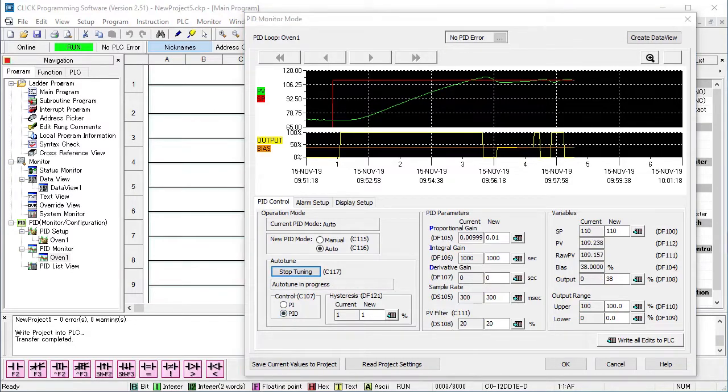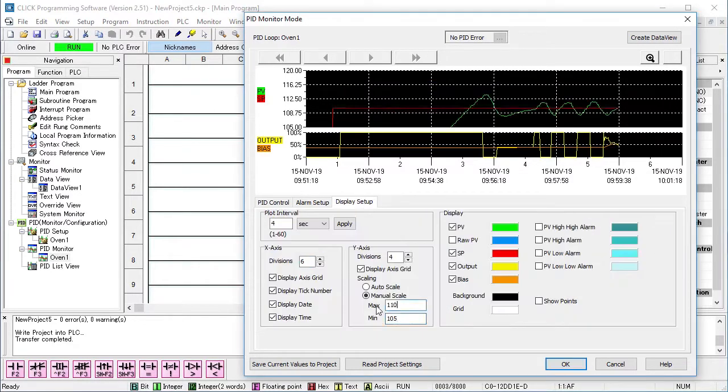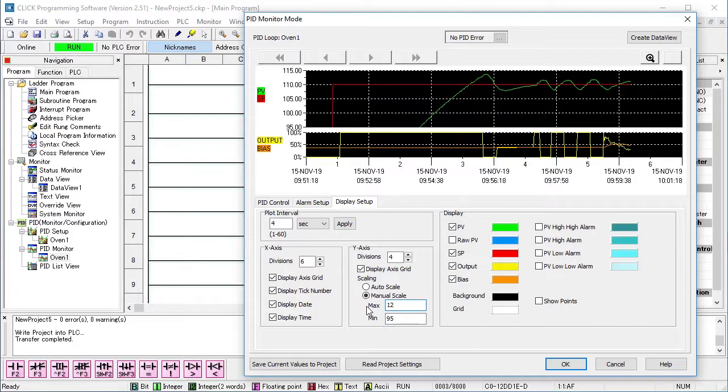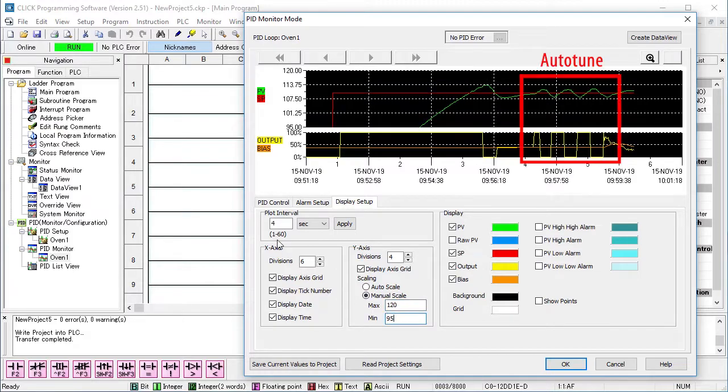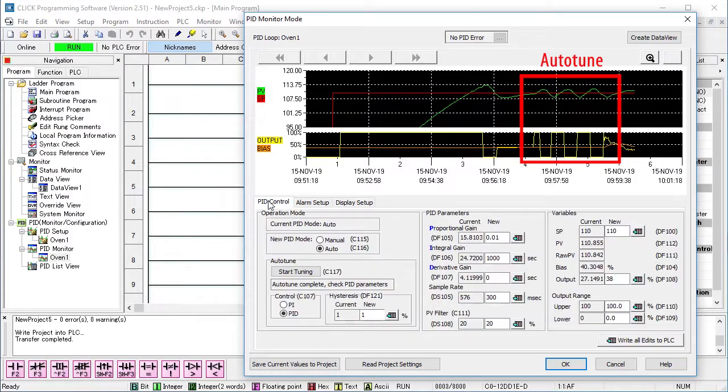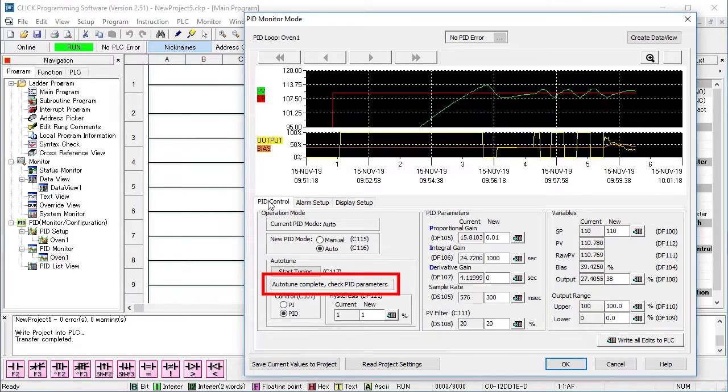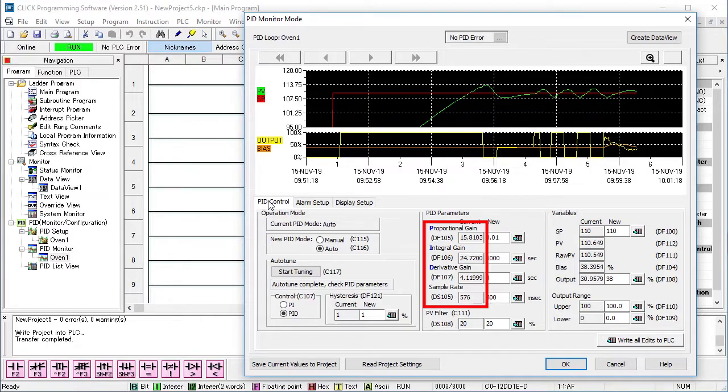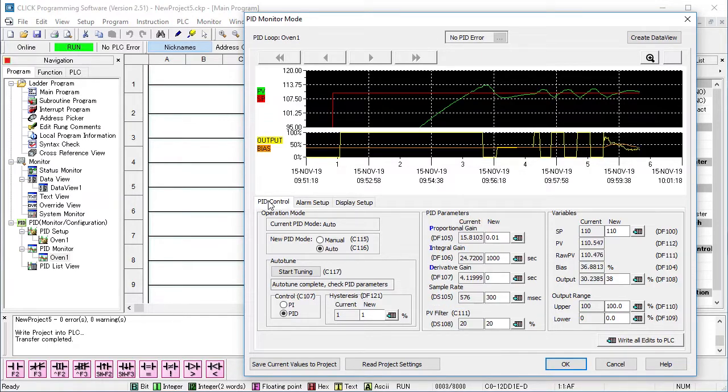I'll fast forward through that. And if I zoom in a little, we see the typical 3 bump auto-tune cycle, the message that it completed successfully and the new PID coefficients and sample time. PID is now running.